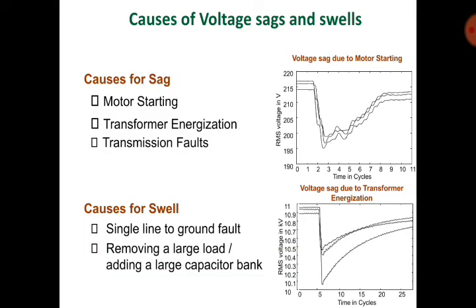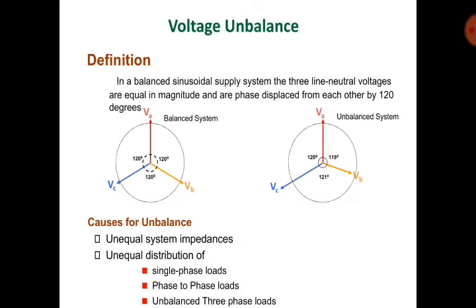Power electronics loads are sensitive to voltage sag. Causes for voltage sag include: motor starting, transformer energization, and transmission line faults. Causes for voltage swell include: single line-to-ground fault, removing a large load, or adding a large capacitor bank.